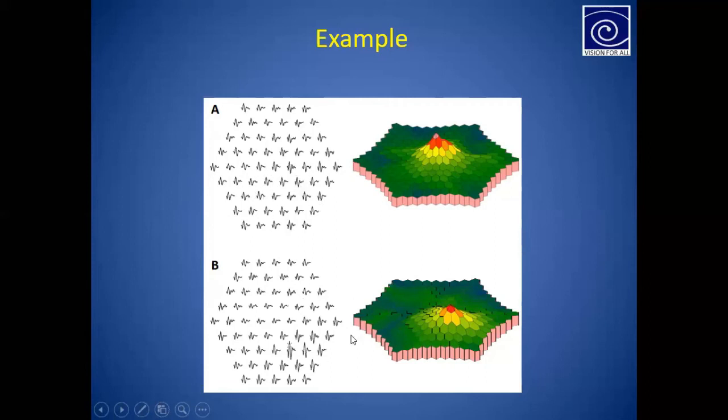But in the other report, due to eccentric fixation of the patient, this maximum response is coming downwards from the fovea, so it is not corresponding to the fovea. So patient fixation is also a very important thing, and we need to watch it very carefully to get a normal report.